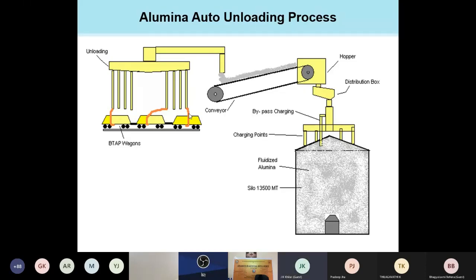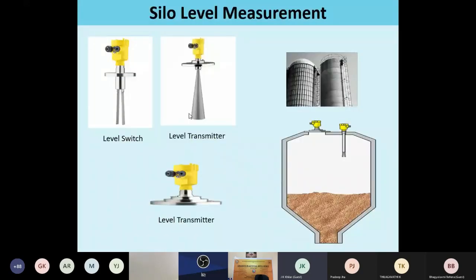For this step, he will just use a knob or select in the SCADA, select the silo, then the whole process will be automatic, that is from the railway wagon to the silo. If the silo level is full, then an indication will come. How will the indication come? Suppose this silo level: these are the level transmitters connected on the top of the silo. The silo is 33 meters in height. On the top of the silo there is this level transmitter, also a level sensor.